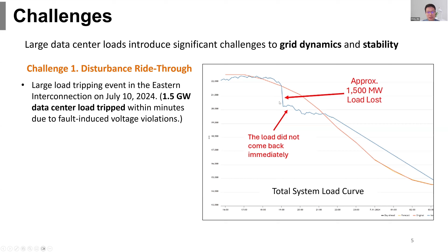For example, a large load tripping event occurred in the Eastern Interconnection in 2024. This figure shows the total system load curve in the Eastern Interconnection, and we can see that about 1.5 gigawatts of data center load tripped within just a few minutes due to a fault-induced voltage violation. Similarly, the ERCOT grid has experienced more than 20 large load tripping events within the recent 2 years. Hundreds of megawatts or even gigawatts of large load suddenly tripping from the system causes serious power imbalance and disturbance to the grid.